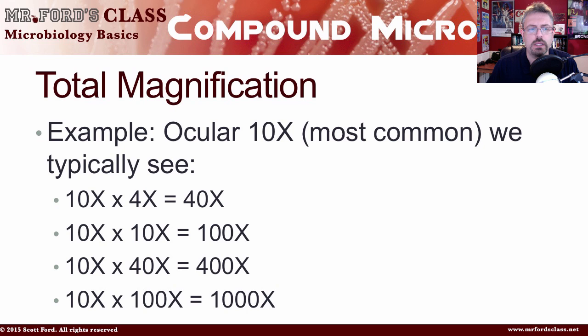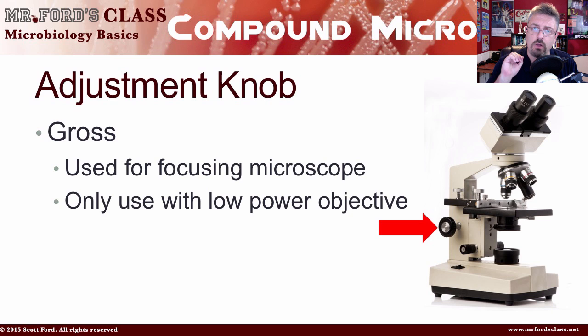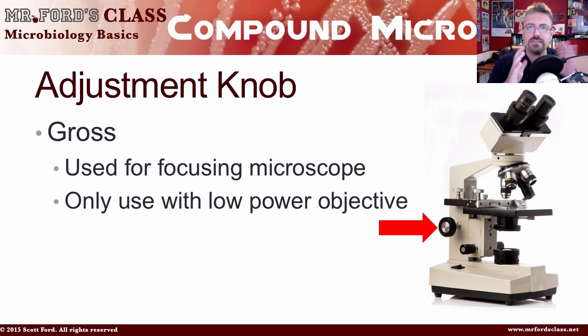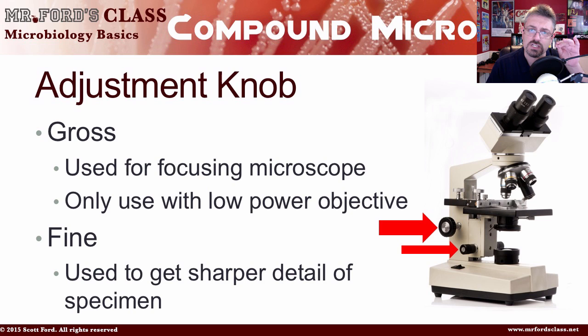The next components are the adjustment knobs — there are two. The gross adjustment knob makes large movements and is used on your lowest power to scan around on the stage. Once you get the specimen into focus and switch to a higher objective, you use the fine adjustment knob, which makes small changes in focusing to get sharper detail. You should not use the gross adjustment knob on high power — that's a no-no.